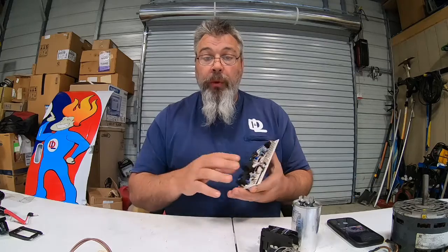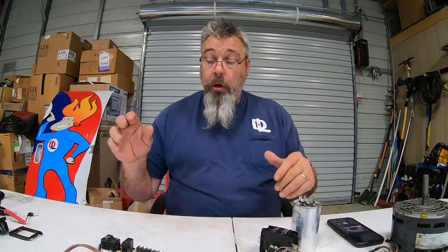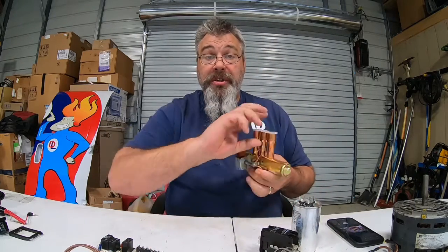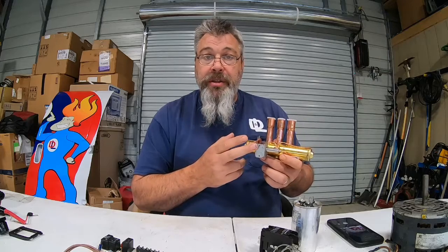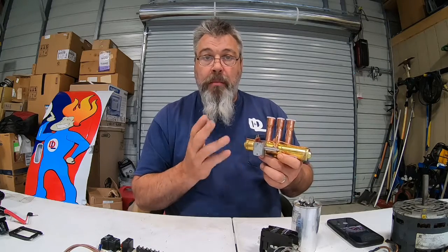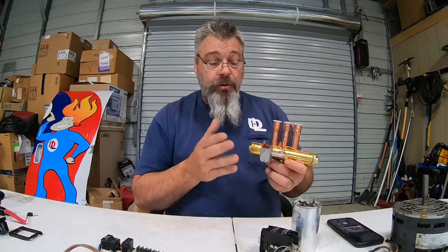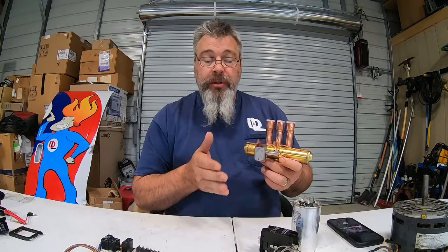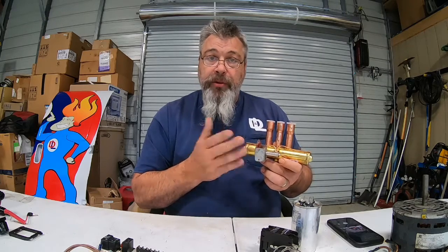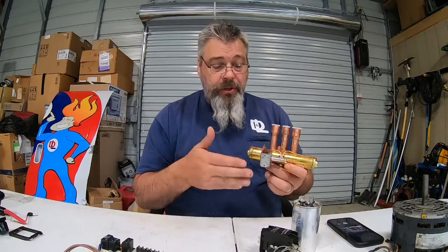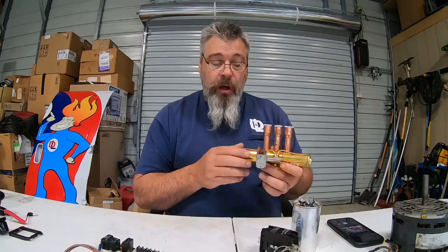So when that goes into defrost, it brings me to my next component. Normally we hear it go like a set of air brakes going off on a trailer or something, and when that energizes, it shuts the condensing fan motor off. In some models, some manufacturers, it'll energize or de-energize. For informational purposes, it'll energize the reversing valve.